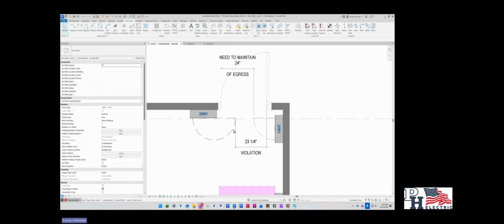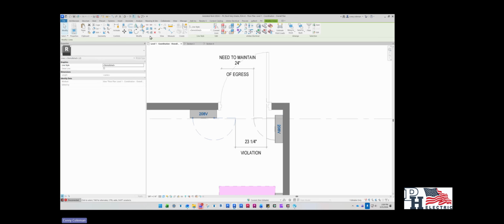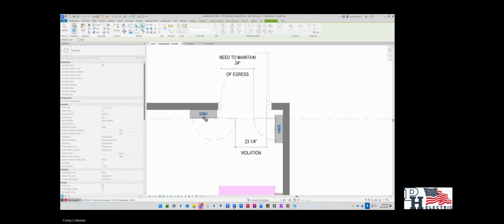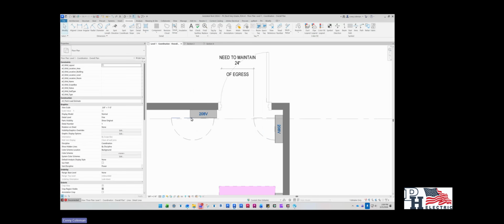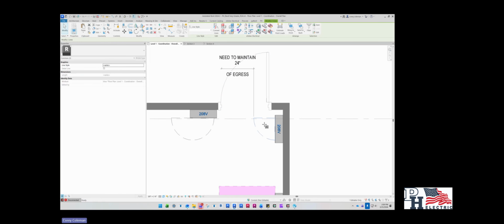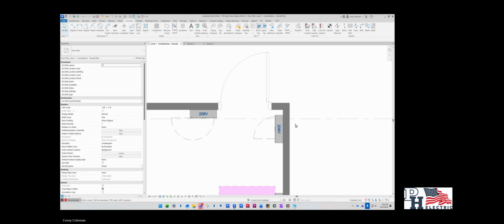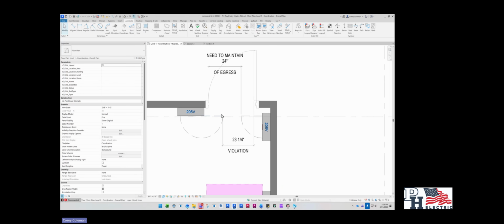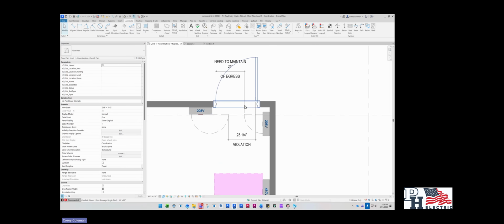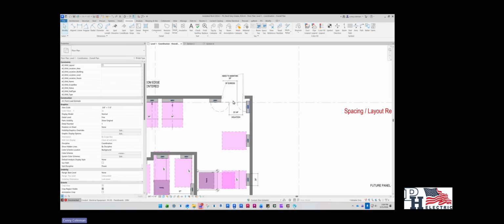This right here, if it is a door that swings all the way open 180 degrees and you do not have that 24 inches of clearance, this would be a code violation. If the panel door swings the other way, for instance, this would be no problem, as the door is not even going to be hindering the exit way. However, this one still would interrupt that path of egress. So just be considerate of your doors and try to stay away from the door as much as possible and the path of egress.